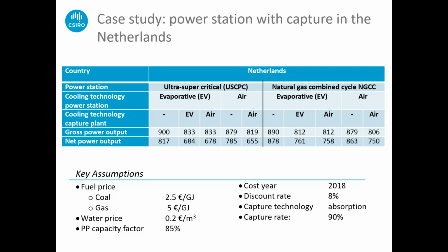We looked at a number of situations there. So for the capture system, you can use evaporative cooling and you can use air cooling as the power plants are, but you can also have this hybrid combination of evaporative cooling for the power plant and air cooling for the capture plant, and that proved to be quite an interesting option for reducing water consumption. Next slide, please, Regina.